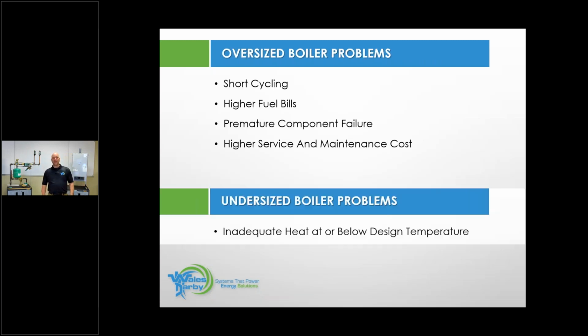Heat load is king. And why is the heat load king? If we oversize a boiler, right? The old method used to be you'd walk across the street, you know, go like this, and if 4 fingers covered the house, that was a 4-section boiler, right? If the boiler had a coil in it, if it was an oil boiler, it had a coil in it, and it only needed a 3-section worth of BTU, you'd put the 4-section in because you wanted the additional BTU to drive the coil. So don't make these assumptions.